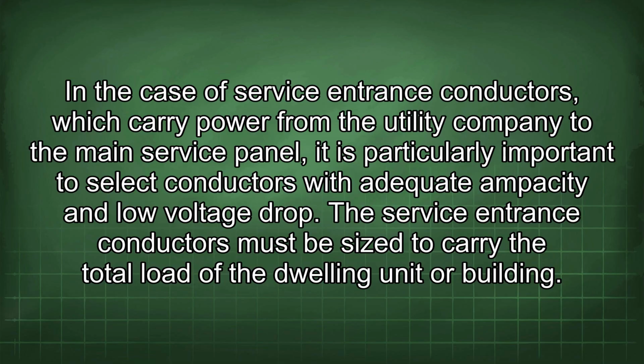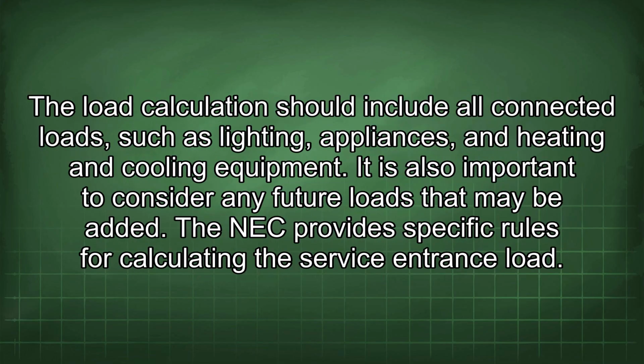In the case of service entrance conductors, which carry power from the utility company to the main service panel, it is particularly important to select conductors with adequate ampacity and low voltage drop. The service entrance conductors must be sized to carry the total load of the dwelling unit or building. The load calculation should include all connected loads, such as lighting, appliances, and heating and cooling equipment. It is also important to consider any future loads that may be added.